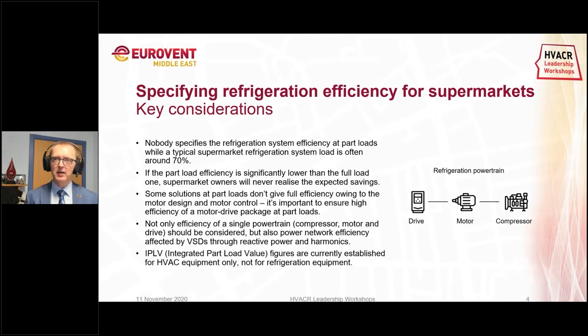When we look at HVAC systems, we have integrated part load value (IPLV) that we can use to compare equipment, but for refrigeration systems that is not widely applied. We needed an approach that emulates what IPLV actually does but in the refrigeration world. That's where a load cycle can easily be established — it doesn't have to be perfectly accurate, just approximately what you would expect at maybe four or eight different load points, depending on how precise you want to get.